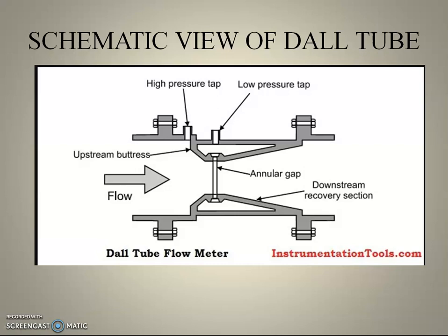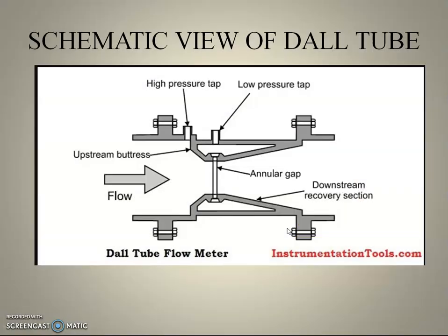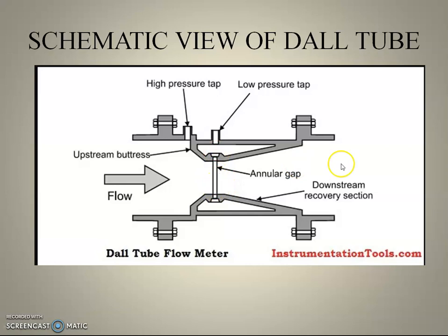In the converging section the pressure is high, and in the throat section the pressure is low. In the construction of the Dall tube, it consists of two tappings: one is the high pressure tapping and the other is the low pressure tapping. The inlet section and outlet section can be split by an annular split, which is used to measure the low pressure in the throat section.